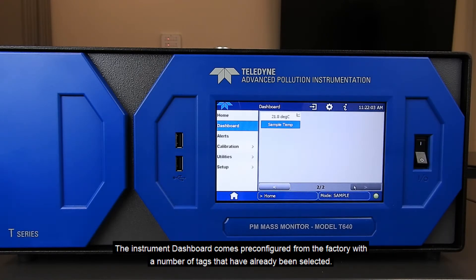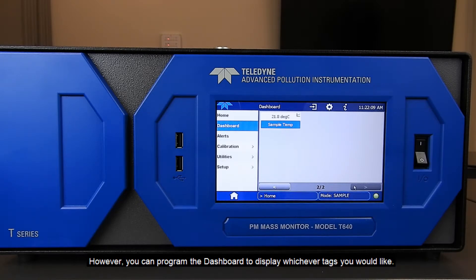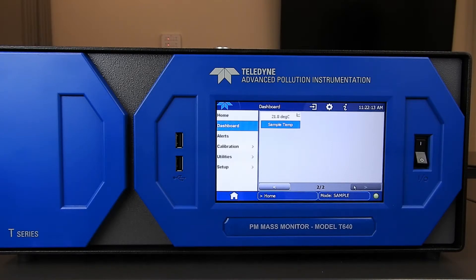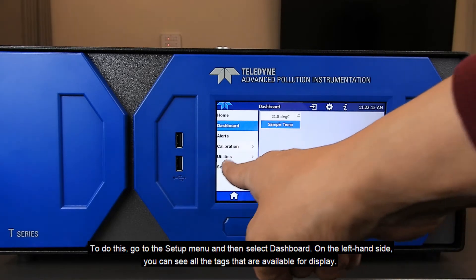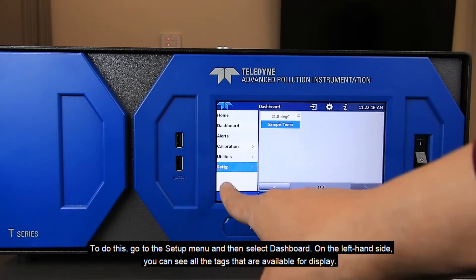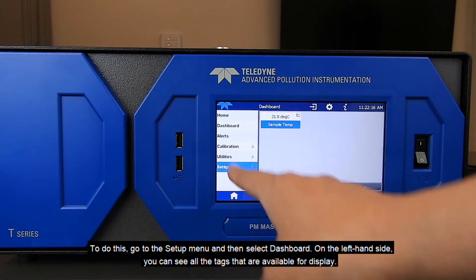The instrument dashboard comes preconfigured from the factory with a number of tags that have already been selected. However, you can program the dashboard to display whichever tags you would like. To do this, go to the setup menu and then select dashboard.